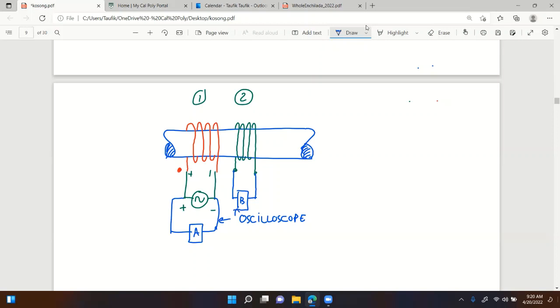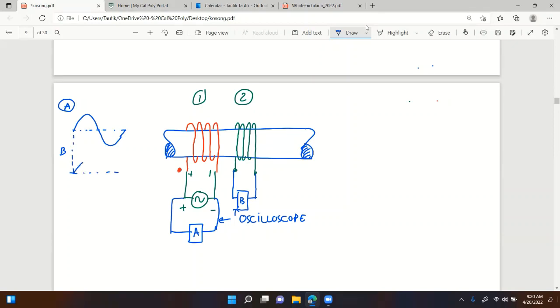Connect an oscilloscope with channel A on the first coil and channel B on the second coil. If they are wound the same way, when you look at the oscilloscope, channel A and channel B will be basically in phase. If they are in phase, that means the channel B terminal is also a dot terminal - they are wound the same way physically.